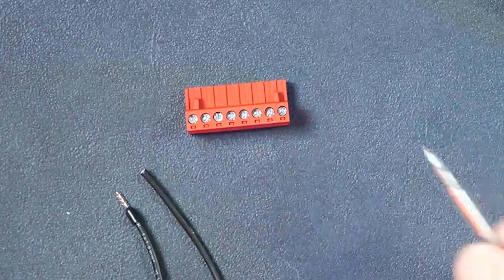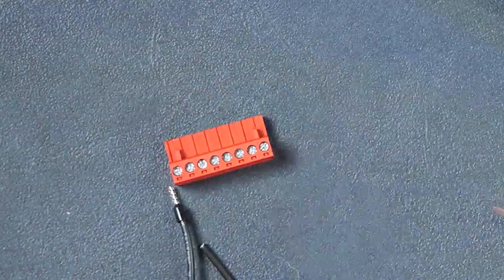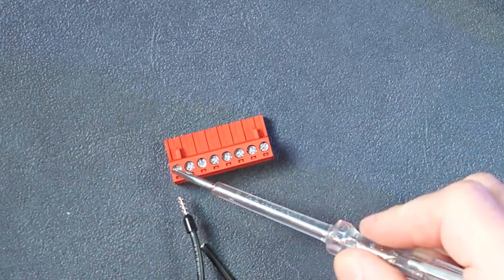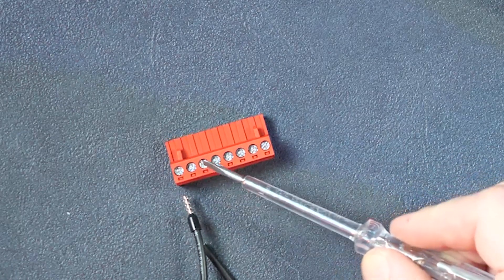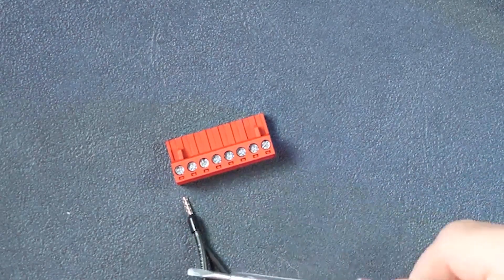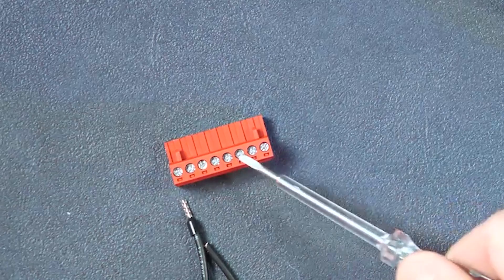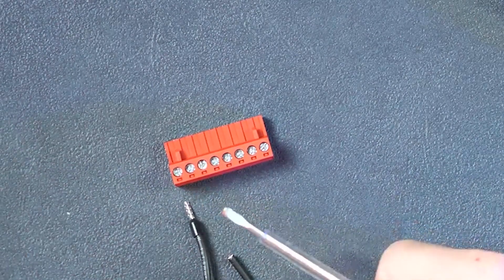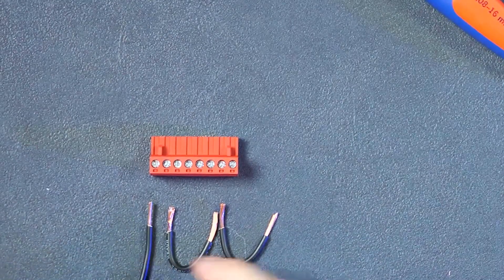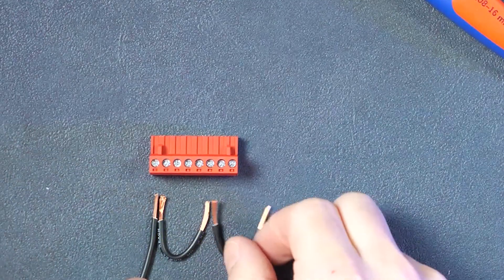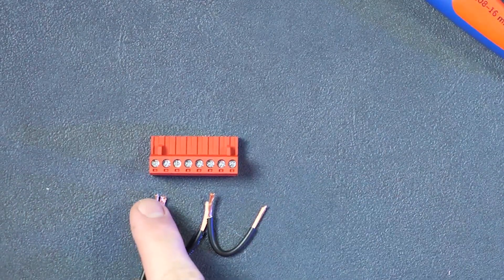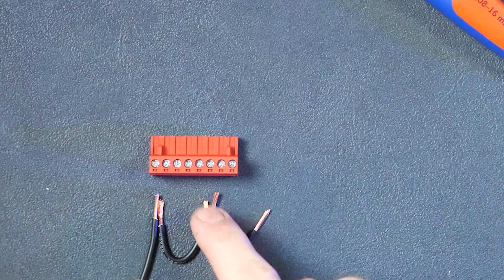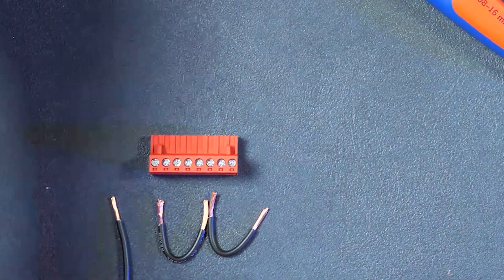It's typically easier to bridge the permanent power from here to the next one to the next one, if all of those loads being switched here are on the same breaker. Of course permanent power coming, then I have prepared these bridges here so we go from relay one input, relay two input, relay three input.